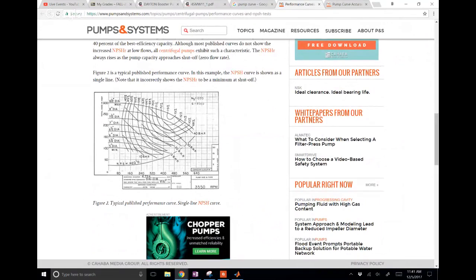Anyway, one of the things about these pump curves is there's an efficiency contour map in there. So it's 40% efficient operating back here. So you kind of want to operate as much as you can right around your best point because it's more efficient. Well, if that's the case, then go ahead and pick this point to find the constant, make it cubic. I mean, quadratic, drop off like this. Because you don't want to be back here or over here anyway. So you kind of want to be, that's 60, I think that's 70. I would try to confine myself around here. I bet that looks like a pretty good place to pick off, just pick the spot off and find that constant.